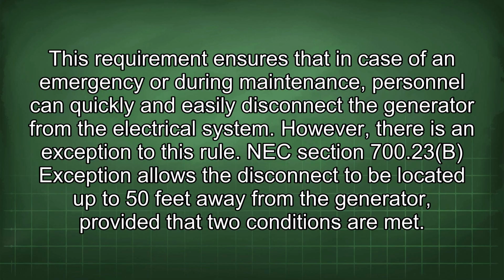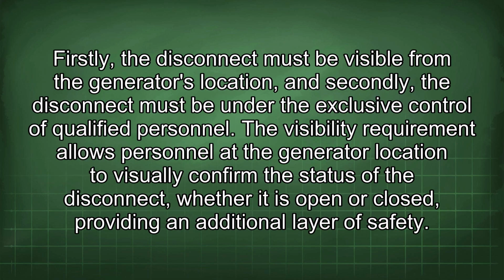NEC Section 700.23b exception allows the disconnect to be located up to 50 feet away from the generator, provided that two conditions are met. Firstly, the disconnect must be visible from the generator's location, and secondly, the disconnect must be under the exclusive control of qualified personnel. The visibility requirement allows personnel at the generator location to visually confirm the status of the disconnect, whether it is open or closed, providing an additional layer of safety.